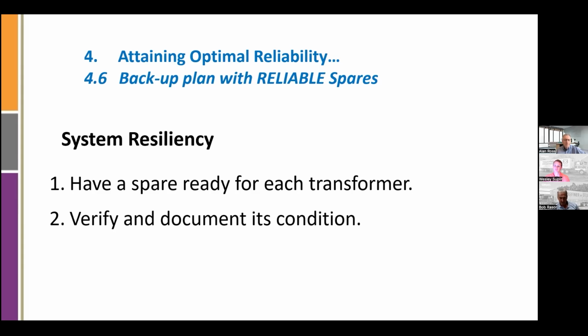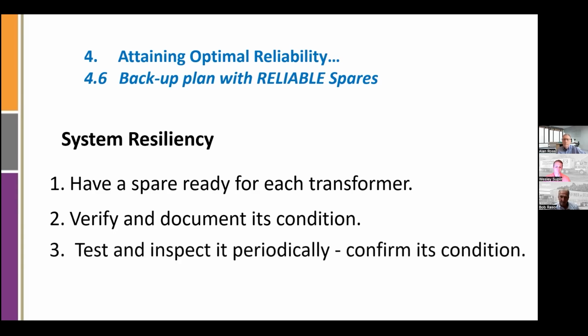Verify and document its condition. The spare may be sitting there in the yard. It may have been taken out of service for a reason: it tripped offline, you saw some gassing in it, you had a spare, you put the spare in, and this other one sits over there, possibly out of sight, out of mind, and you don't really know its condition. It's a great idea to have that spare looked at, upgraded, painted, whatever it would take to have a very reliable spare. And then confirm its condition periodically.